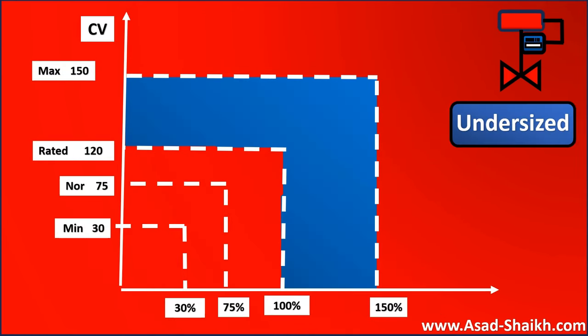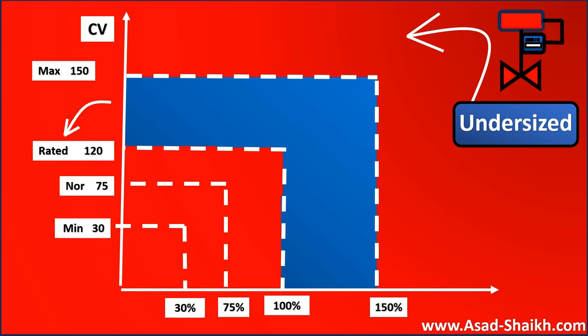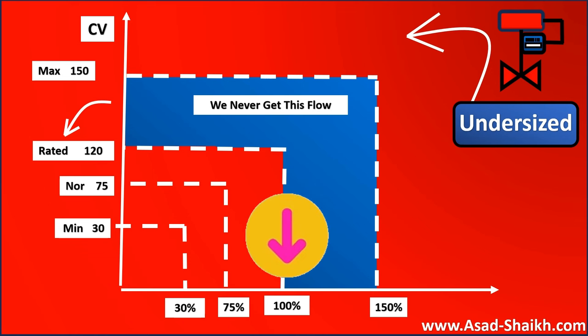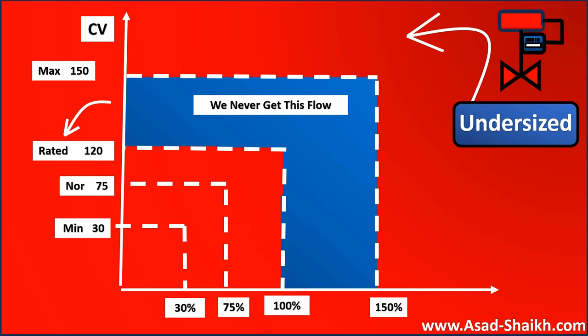Similarly, this is a classic example of an undersized control valve. Here the rated capacity is 120 but the required CV is 150. The control valve is already fully open at 100%, so it will never be able to provide the required flow rate at maximum flow conditions.